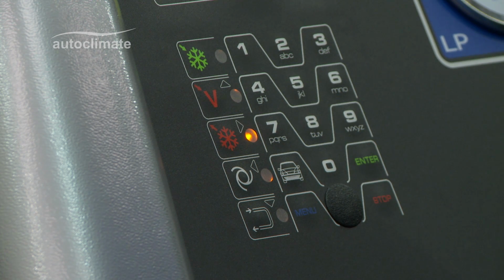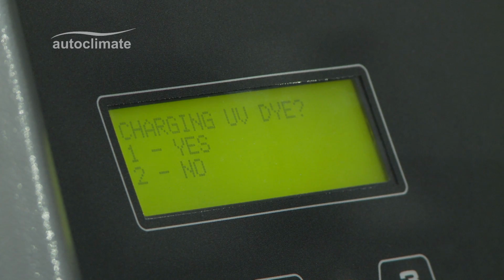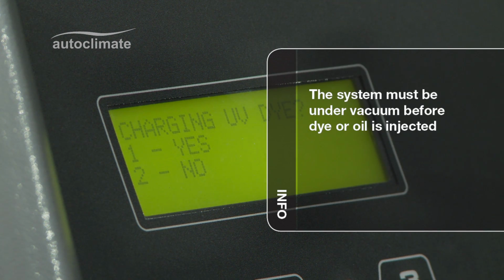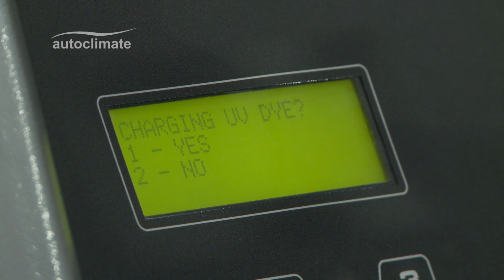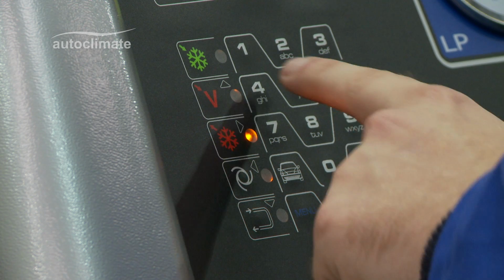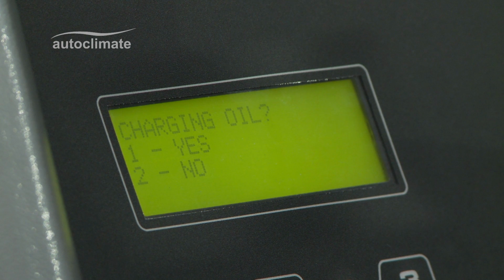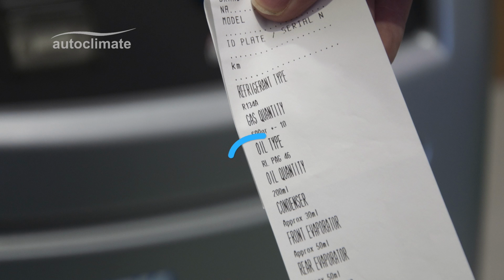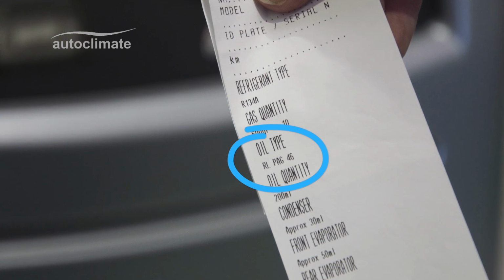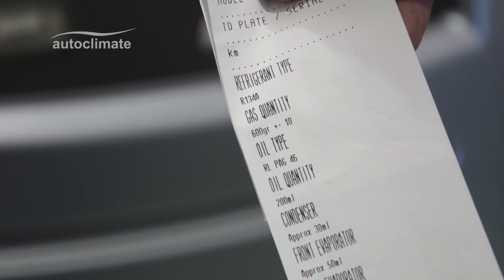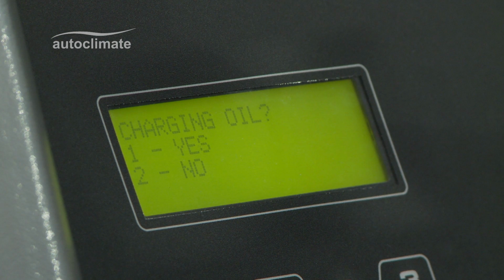Press Enter to continue. A prompt indicates UV dye injection. It is good practice to inject UV dye to make it easier to find any subsequent leaks. Press 1. A prompt indicates oil injection. Some manufacturers recommend oil injection with each recharge. The details are shown on the printout. Press 1 to inject oil.